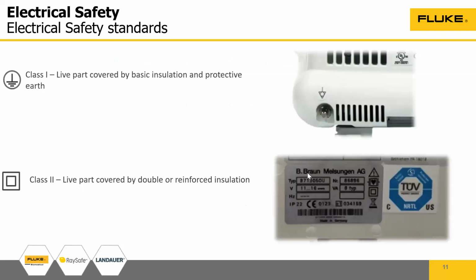Okay, so how do you understand which device is what? If you see any medical device, on the back side, if you turn it around, you'll be able to see these symbols. A class 1 medical device will be on the top left, and at the bottom is a class 2 medical device. This is how you'll understand whether it is a class 1 or class 2 medical device, and this will help you decide what kind of testing you need to do.